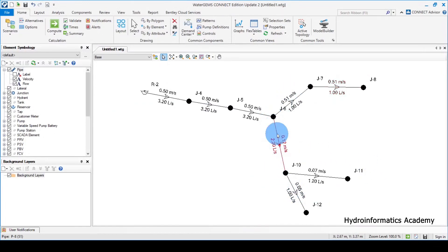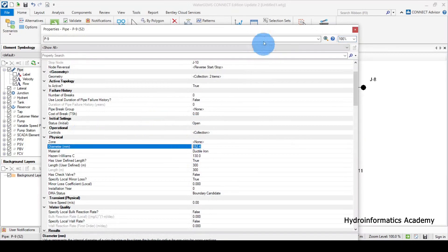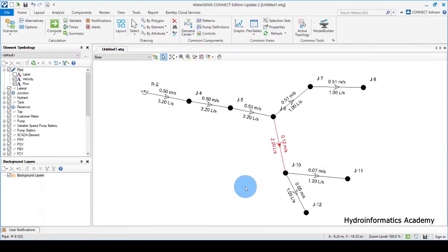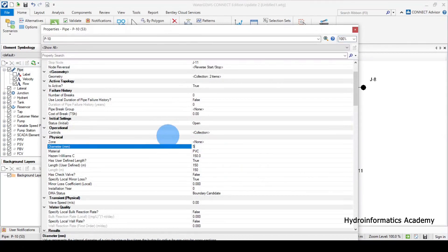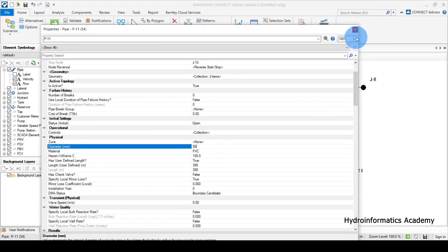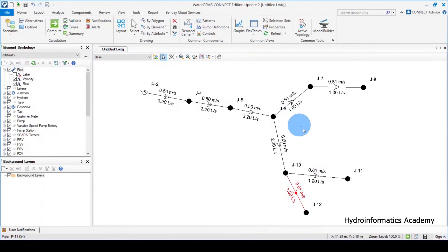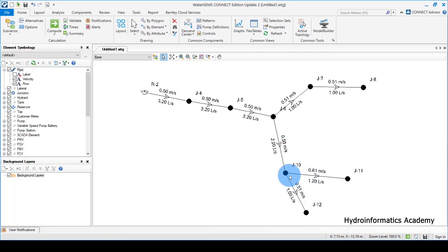For this branch, I also need to change the pipe value. I'll start with 75, then try 50mm for this link and also adapt 50mm for this region here. After running, the flow here is 2.2 liters per second — that is the summation of the base demands assigned to these junctions. We have 0.6 and 0.51, which are both within the acceptable velocity range of 0.4 to 0.5 all the way to 1.5 meters per second.